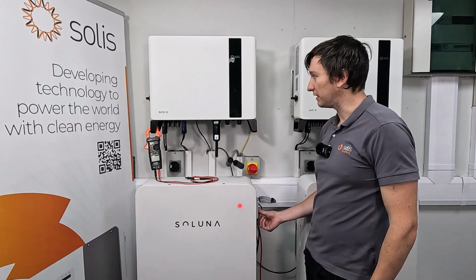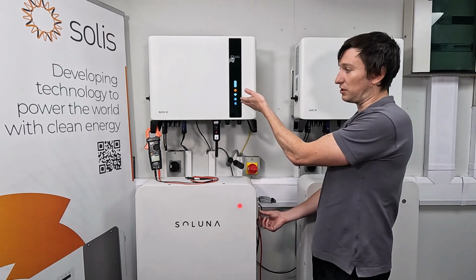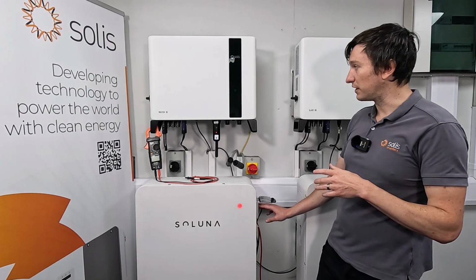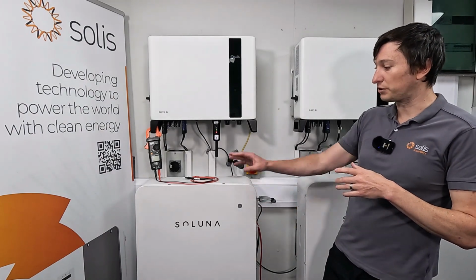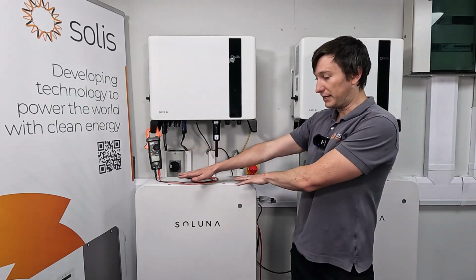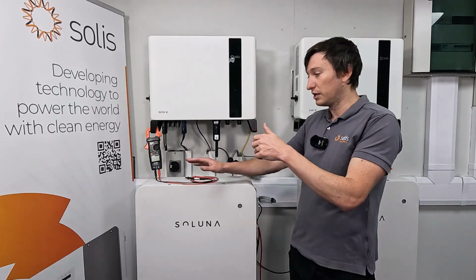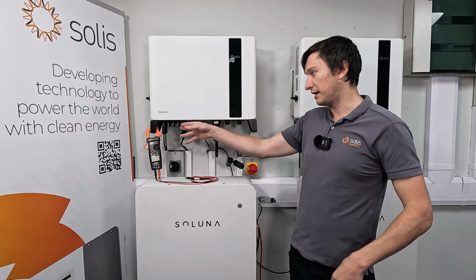And there we go - there's the good click, and we're starting up the inverter. Let's turn it off nice and quickly so we don't get alarm codes and so forth. We've confirmed now that battery power connections are good. If the polarity was wrong, it wouldn't start up - and if your polarity on your solar was wrong, it also wouldn't start up.